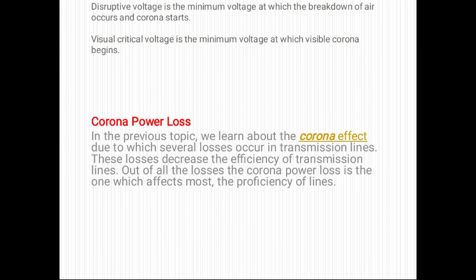There are two terms. One is disruptive voltage and second is visual critical voltage. Disruptive voltage is the minimum voltage at which breakdown of air occurs and corona starts, and visual critical voltage is the minimum voltage at which visible corona begins or starts. Now power loss due to corona.